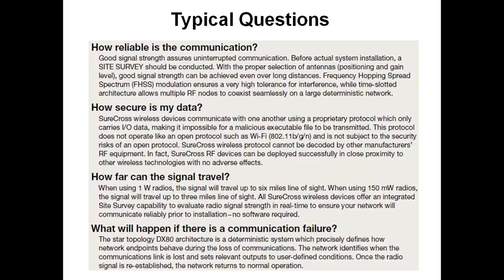The first one is, how reliable is the communication going to be? What you'll find out as we go through this today, we actually have the ability to do a site survey, which is really just an RF signal strength indicator. That'll basically tell us if we can get from point A to point B. Underneath the hood, we'll be doing some things called frequency hopping spread spectrum. That's really just part of the proprietary protocol, which allows us to jump around on that 902 to 928 frequency band. We'll go into this in more detail. But basically, with what we're doing, we have very robust communications.